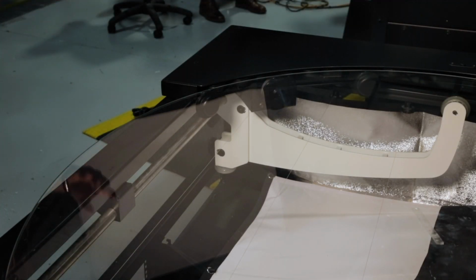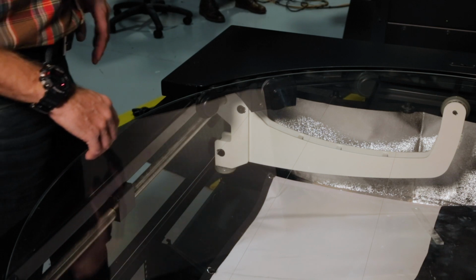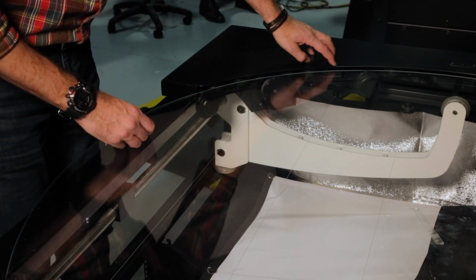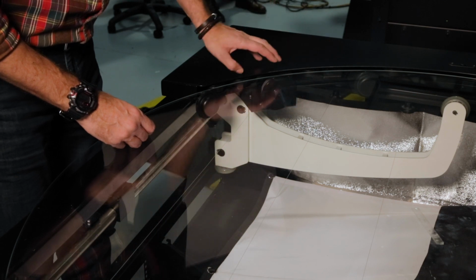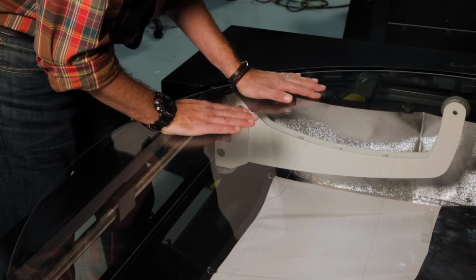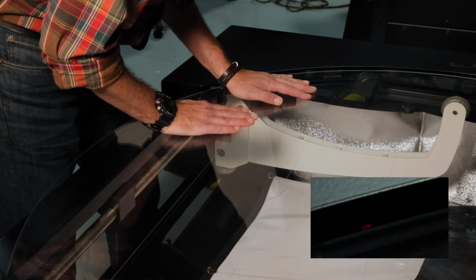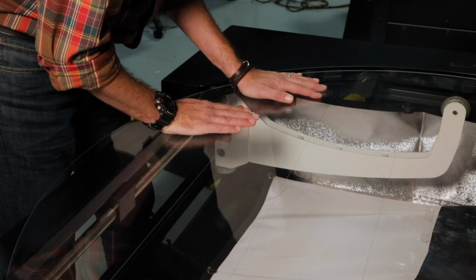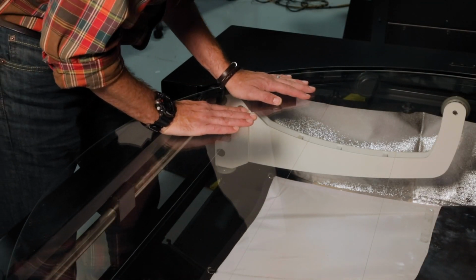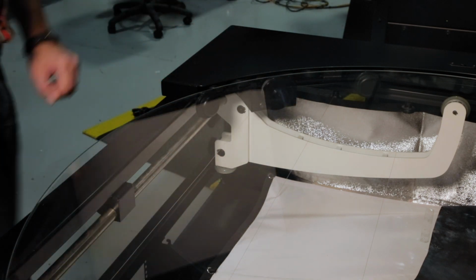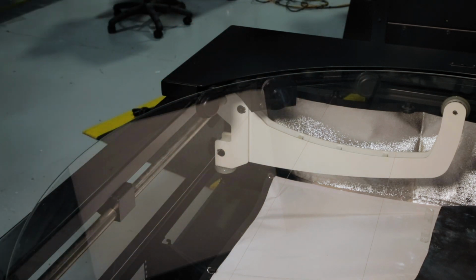Unlike the magnetic sensor that has 2 pieces that you put into position, the optical sensor is mounted permanently under the covers to the side of the left drive motor, and it utilizes a notch on the underside of the glass. You're going to need to lean over to look at the optical sensor and look for the red LED light. After you see the LED light, rotate the glass by pushing on the top of it until the notch on the underside of the glass is in front of the optical sensor. You're going to want to rock it back and forth until you get in the right position, until you see the LED light shut off, and you're ready to begin the calibration sequence.